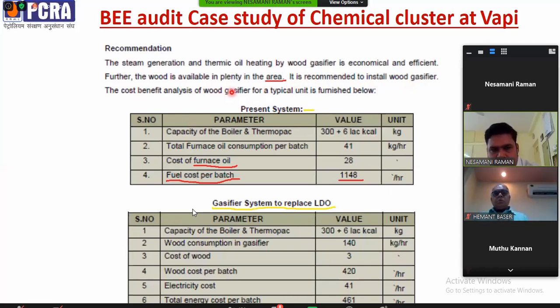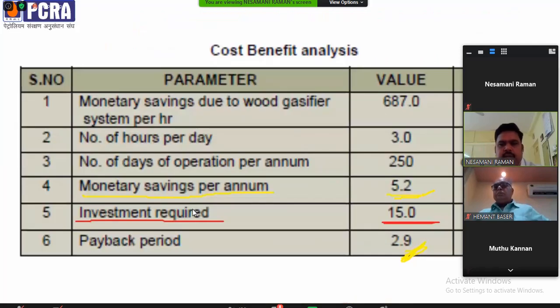The cost benefit analysis of a wood gasifier for a typical unit is as below. The capacity of the boiler plus thermopack of one industry is 300 plus 6 lakh kilocalories. For that, presently they were using furnace oil. The fuel cost per batch was 1148 rupees per hour. If they replace the furnace oil with the gasifier system, the energy cost per batch will come down to only 461 rupees per hour. So the monetary savings in energy cost is almost 687 rupees per hour.